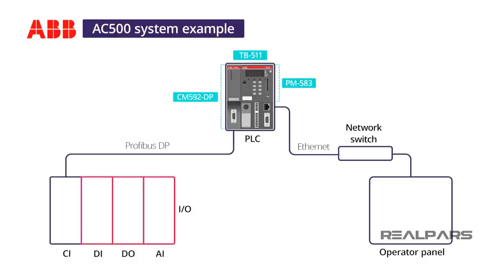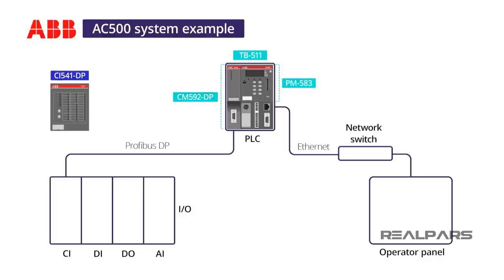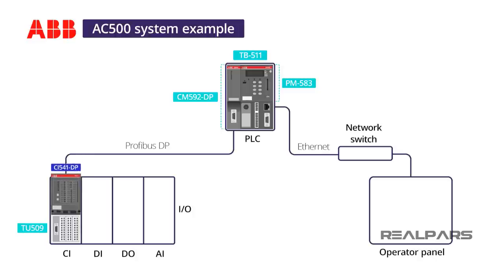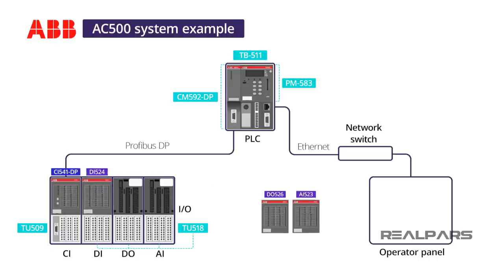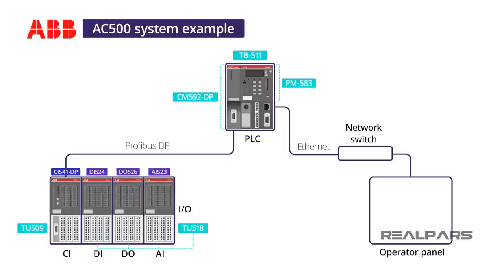To support the three I/O cards in a remote configuration, I first need a Profibus interface card in the I/O panel to communicate with the CM592DP card on the CPU terminal base. I select a CI541DP Profibus card and a TU509 terminal unit base. I will need three TU518 I/O bases: one for a single DI524 32-point 24V DC digital input card, one for a DO526 8-point 24V DC digital output card, and one for an AI523 16-point analog input card.